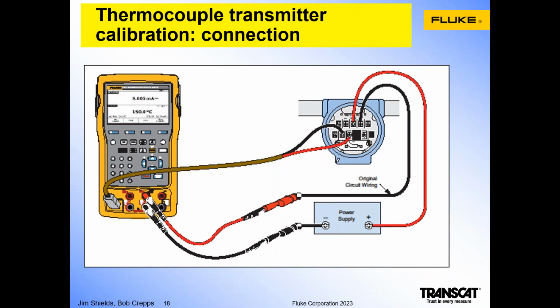Once in the field, make the connection. In this instance, we'd be using an external power supply rather than the internal 24 volts from the 754. The thermocouple output of the calibrator is connected to the temperature input of the transmitter, and the milliamp signal is being measured, and the 4 to 20 milliamp signal is being analyzed and calculated for error.